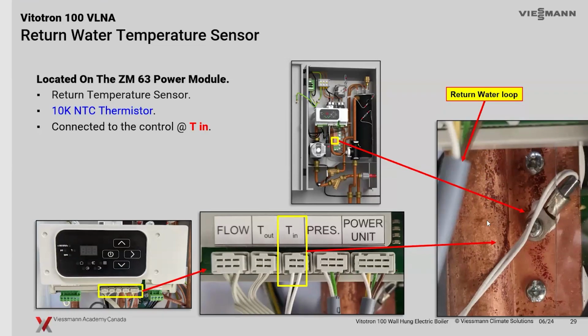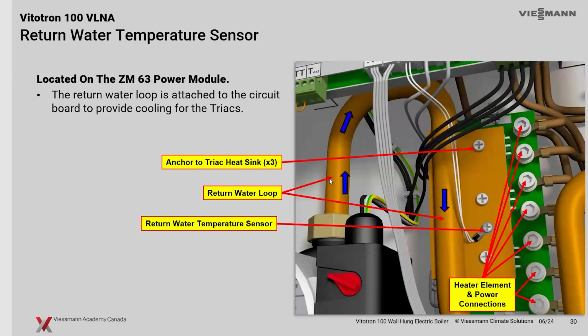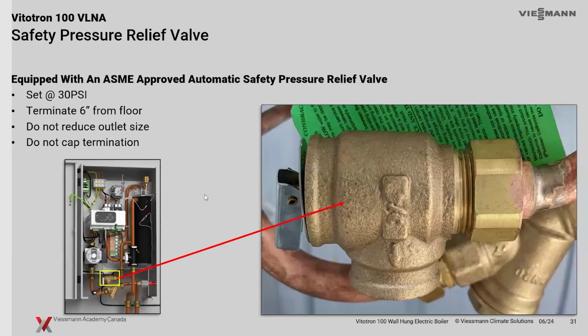So the return water goes back through and we make contact with this little circuit board. The idea behind that is that as that return water comes in, this little board here is going to heat up with that 240 volts, operating off the resistors. This is actually going to pick up a little bit of heat from that, cool that board down, and keep that board essentially acting like a little heat sink for that little triac board, just to keep it functioning longer in your system, right? They wear as they heat up and that sort of thing. So very nice little added thing here to use that water to cool that system down. And we've got a little sensor to pick up what that return temperature is.